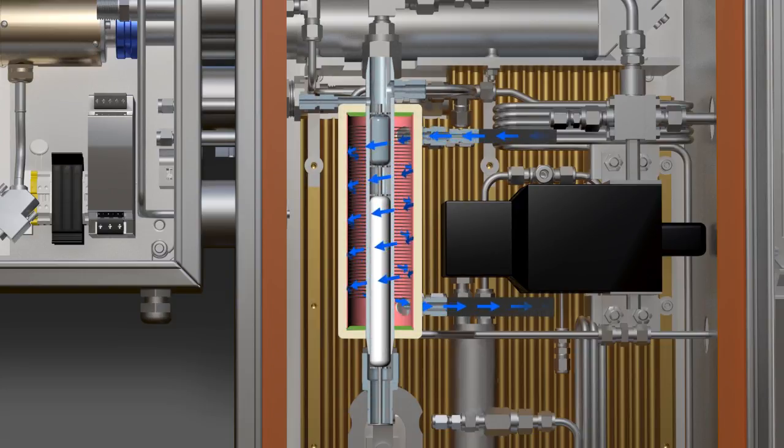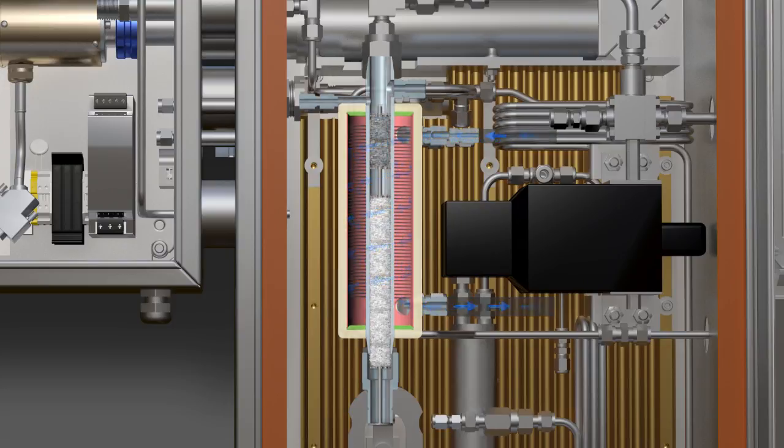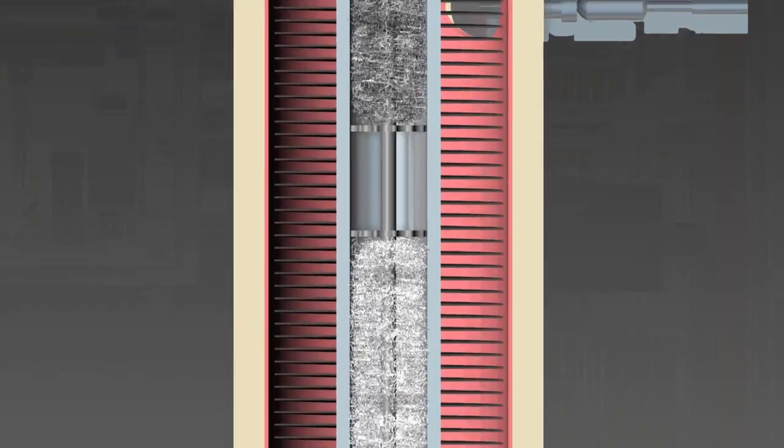As the tail gas enters the analyzer, the newly designed internal demister removes entrained elemental sulfur mist from the gas stream using dual teflon and stainless steel demister pads.